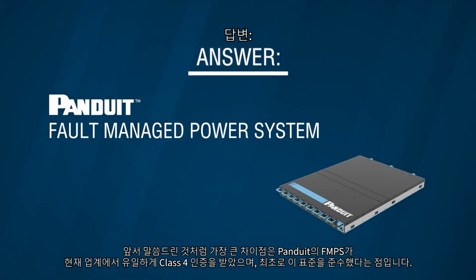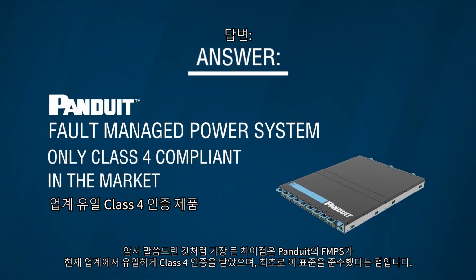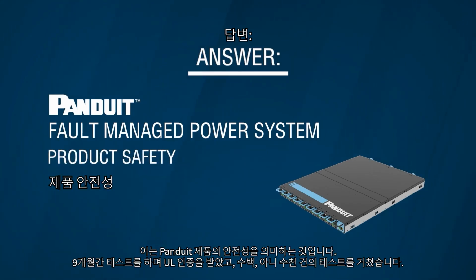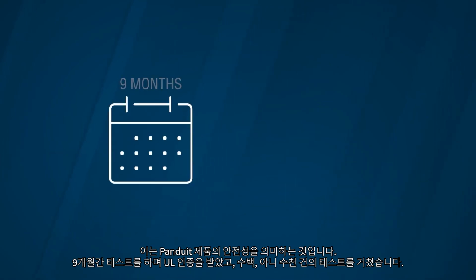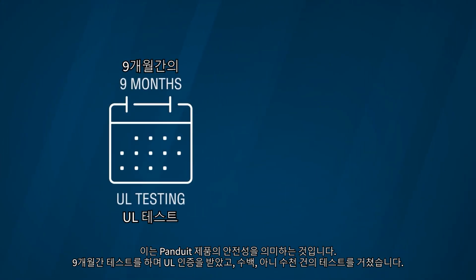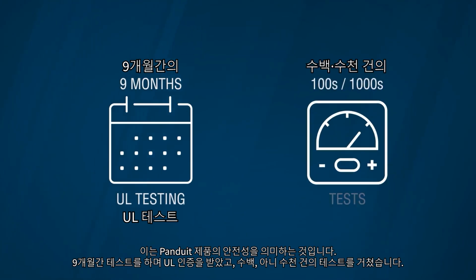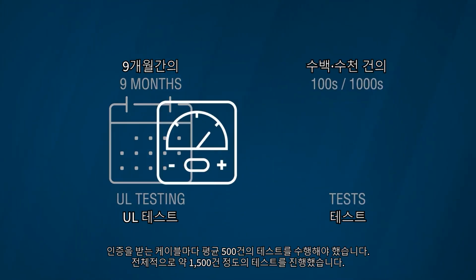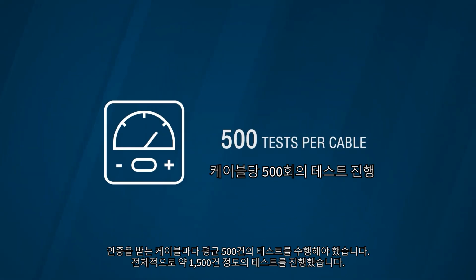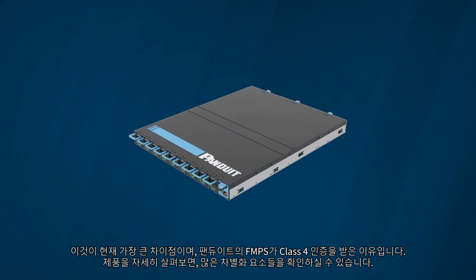The biggest difference is that Panduit's system is the only Class 4 system in the market today, and basically the first to ever comply with it. What that speaks to is the safety of the Panduit product. It speaks to the 9 months of testing that we had to go through with UL, hundreds, if not thousands of tests. We've had to do 500 tests per cable that we want to list with. On average, we did about 1,500 tests overall. So that's our biggest difference today, being Class 4 listed.